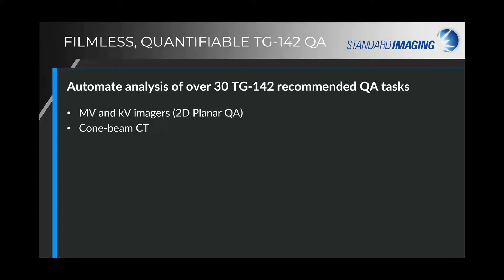The cone beam CT utilizes the Catphan phantom from Phantom Laboratories, typically included with Varian or Elekta cone beam systems. Our MV and KV 2D planar QA uses our QC-KV and QC-3 phantoms. For MLC QA tests, we have both image-based tests — including the picket fence test, leaf transmission, and leaf position — and log file-based tests, which are a true leaf speed analysis calculating and reporting feedback on each individual leaf speed within the MLC chain.